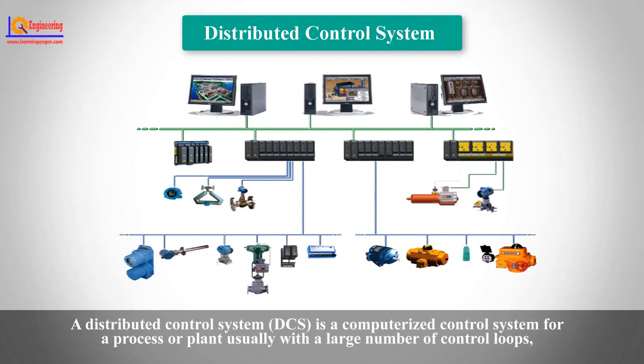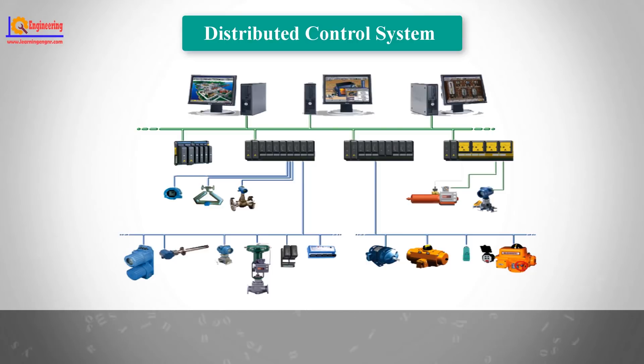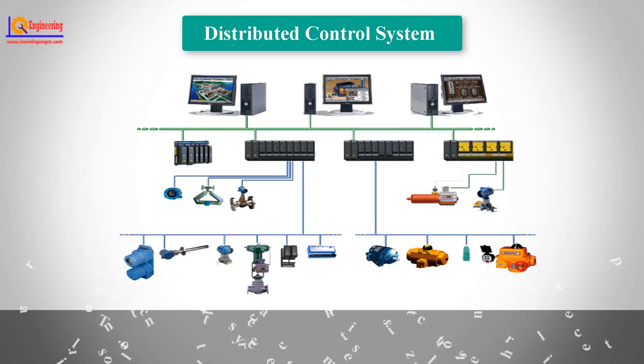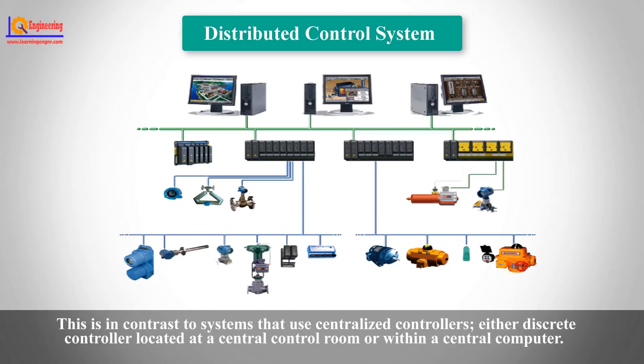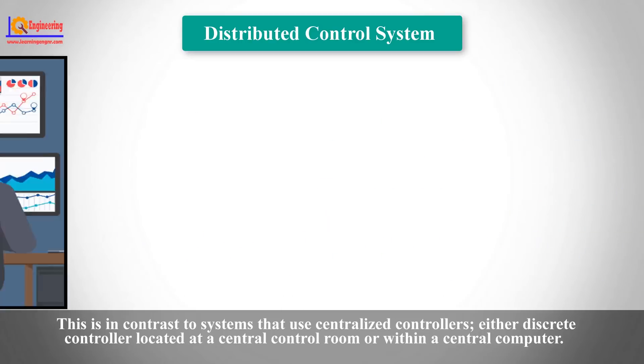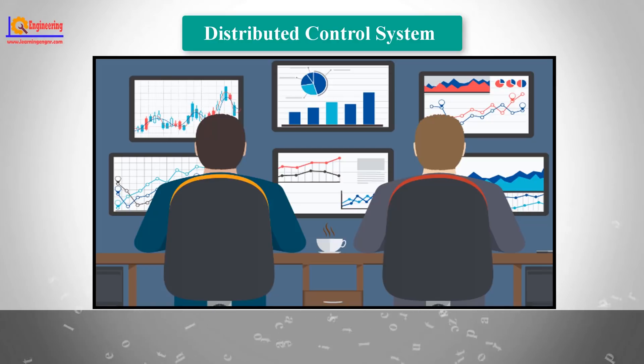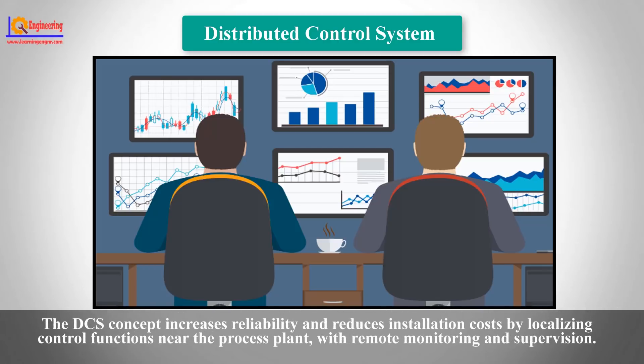A distributed control system is a computerized control system for a process or plant, usually with a large number of control loops, in which autonomous controllers are distributed throughout the system, but there is central operator supervisory control. This is in contrast to systems that use centralized controllers, either discrete controllers located at a central control room or within a central computer. The DCS concept increases reliability and reduces installation cost by localizing control of functions near the process plant with remote monitoring and supervision.